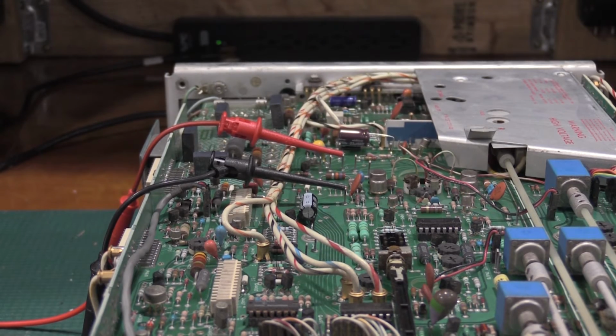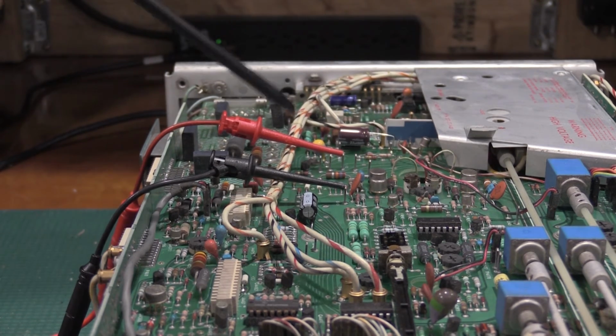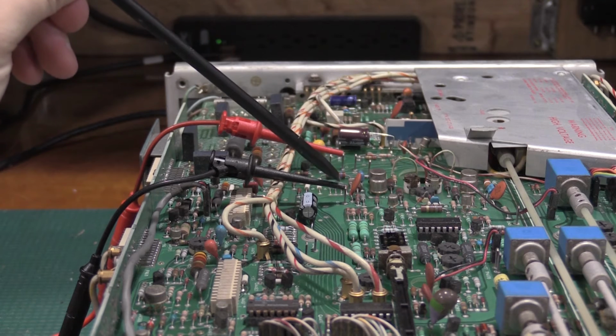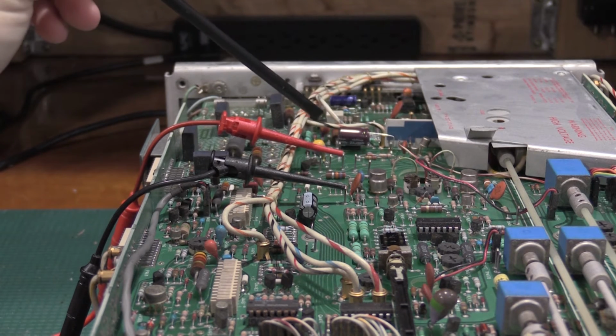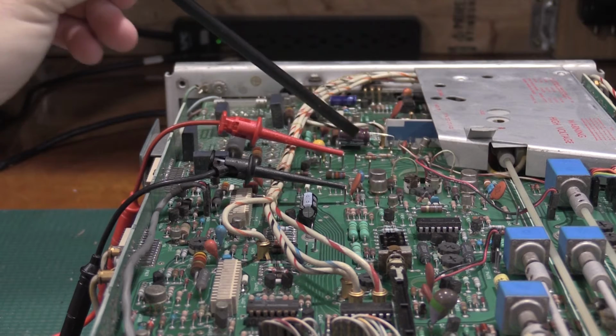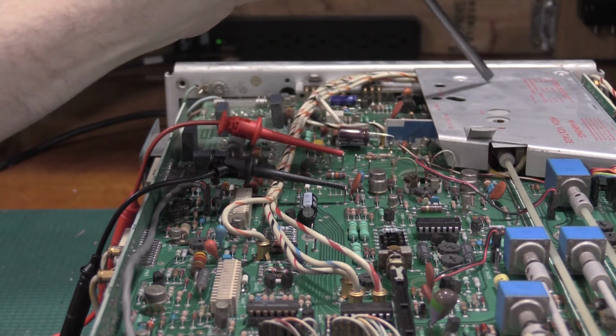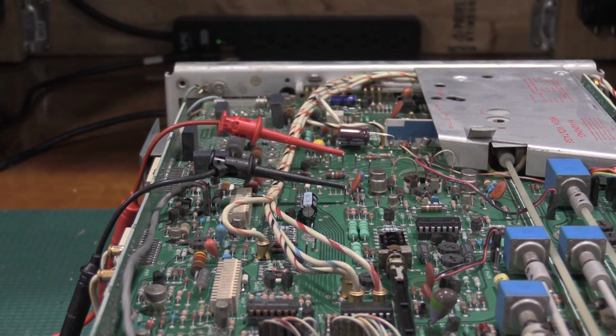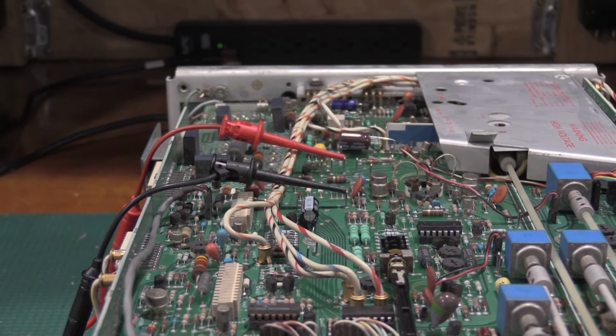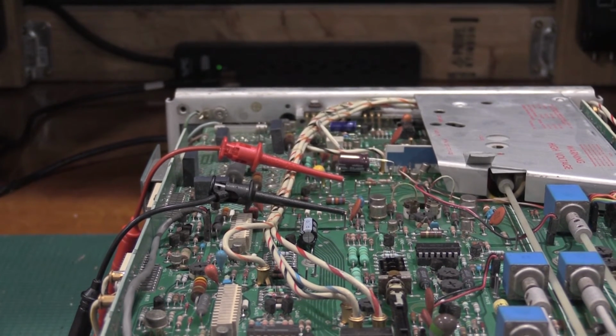Okay, here's the 55 volt test points. I'll be using this test point for ground for all of them. The power supply test points are right here. The high voltage is under here. We'll get to that shortly. Meter settings are 10 power line cycles with the filter on, and 10 readings for average. And currently I have 55.01 volts.